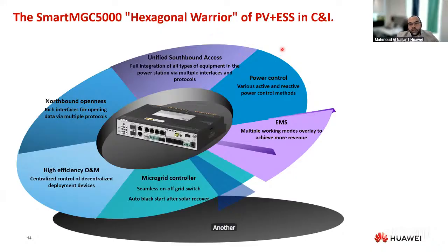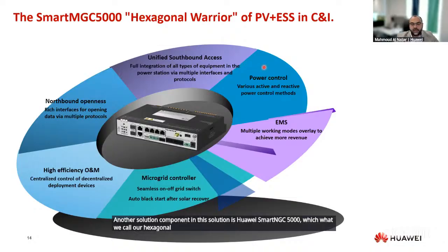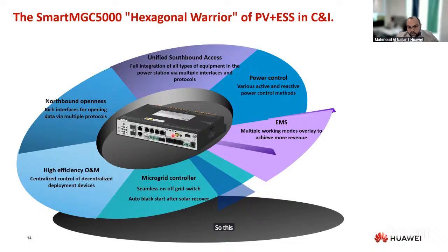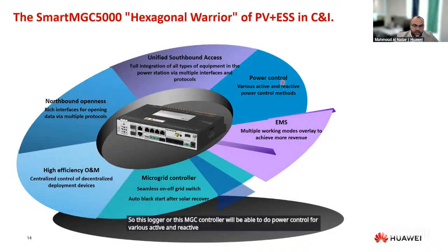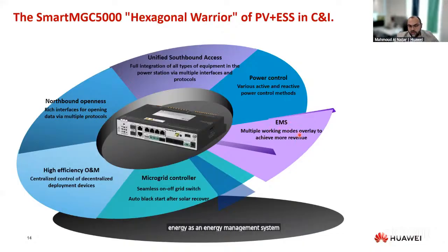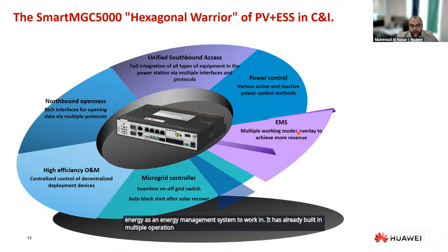Another very important component in this solution is the Huawei Smart MGC 5000, which we call our hexagonal warrior in the PV and energy storage C&I. This logger, or this MGC controller, will be able to do various active and reactive power control actions. It is capable of acting as an EMS, an energy management system. It has multiple operation modes built in. Within these operation modes, it can act as a microgrid controller. It can centralize your control for all the decentralized components by high efficiency operation methods.